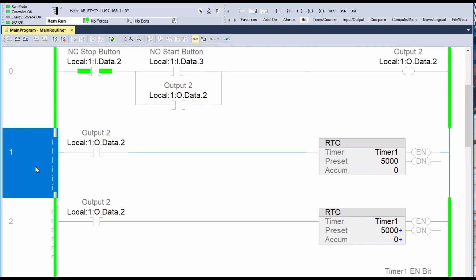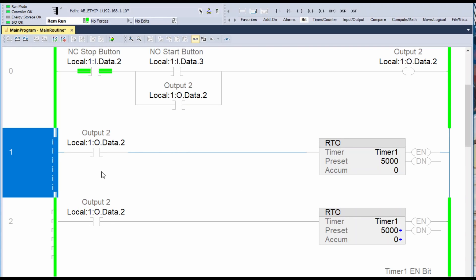Then you've got two rungs that are now available with identical instructions on them. The small 'i' right here — these will change to the larger 'I' once we accept the changes. But the small 'i' right now is the insertion rung — this is what's going to be inserted into my program. The 'R' is the replaced rung, so this is my original rung and it's going to be replaced by the insertion rung.